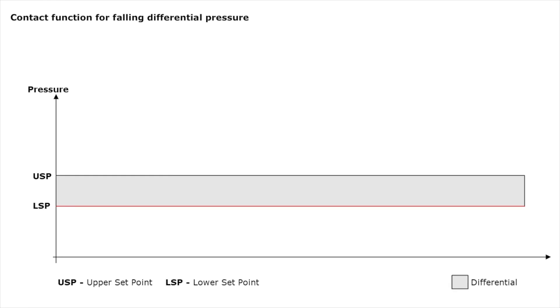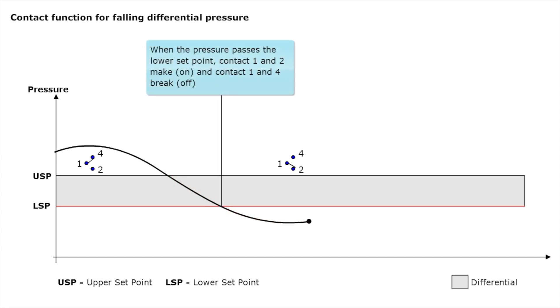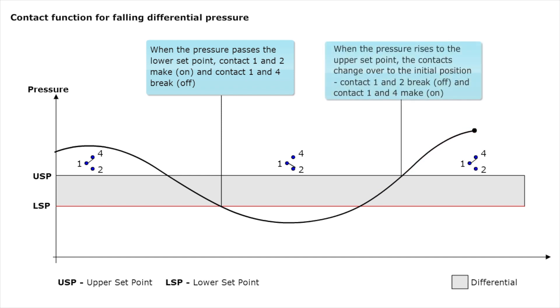Let's look at the contact function for falling differential pressure. When the pressure passes the lower setpoint, contacts 1 and 2 make and contacts 1 and 4 break. When the pressure rises to the upper setpoint, the contacts change over to the initial position. Contacts 1 and 2 break and contacts 1 and 4 connect.